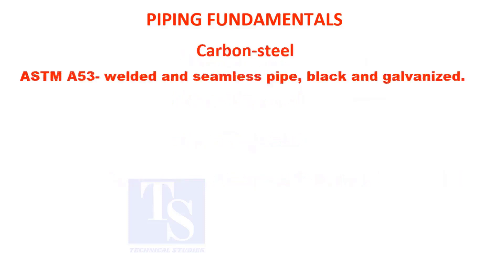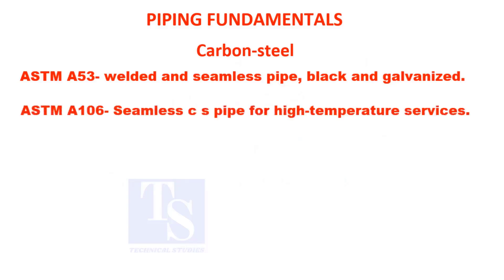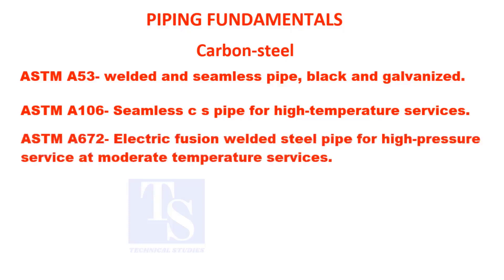ASTM A-53: welded and seamless pipe, black and galvanized. ASTM A-106: seamless carbon steel pipe for high temperature services. ASTM A-672: electric fusion welded steel pipe for high pressure and moderate temperature services.